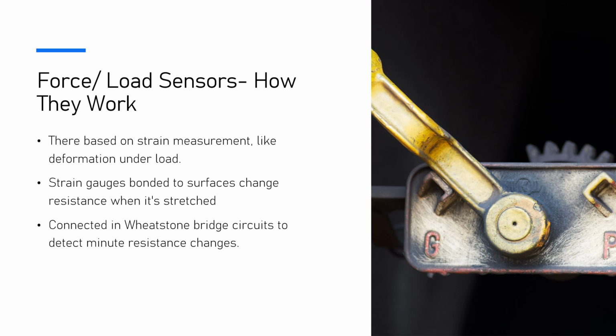Then there's the Wheatstone bridge circuit, where multiple strain gauges are arranged in a bridge configuration. The resistance imbalance creates a small output voltage, producing a weak analog signal that is amplified and converted into readable output signals, such as digital displays or PLC inputs.